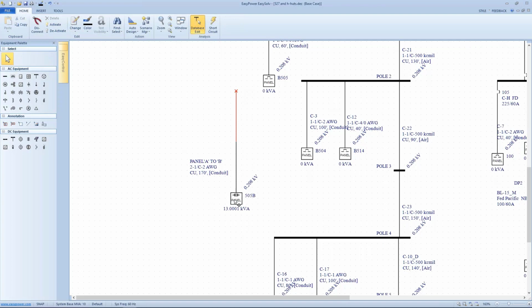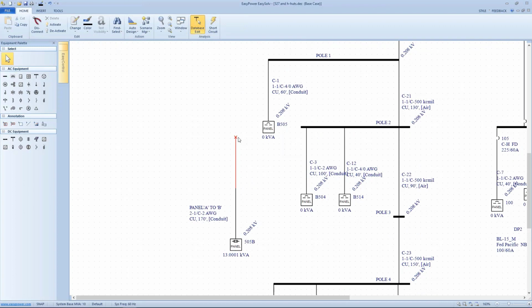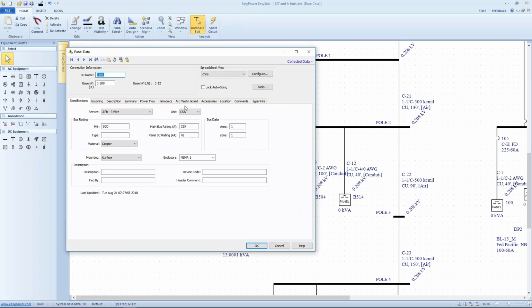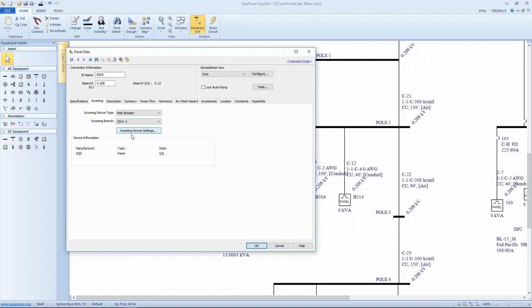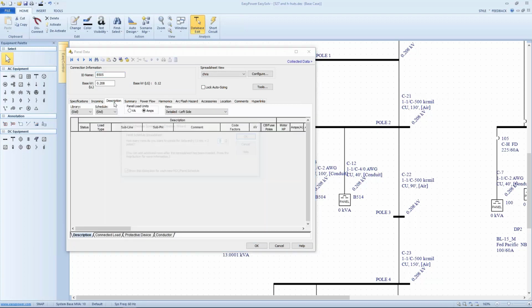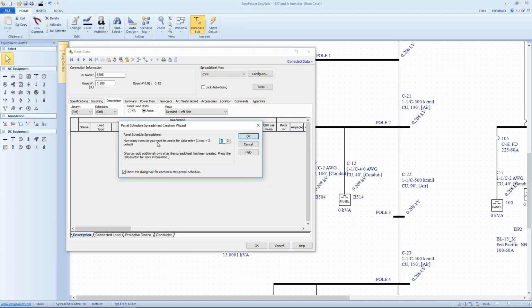All right, so we have a panel set up, and we need to tie it into an existing panel. The way the tool works is literally just connect it to the panel, indicate where you want it coming in. Now, we've already labeled the cable. When we come into the panel, we can see that we've set this up. We've got capacity ratings on it. We've set the incoming device. But under description, we haven't told it what the panel schedule looks like.